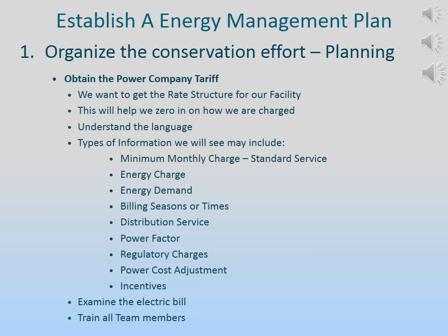This bill is a flat rate consumption, so anything we save is at the 5 cents per kilowatt hour. Also notice with this tariff, there are flat rate facility charges that we cannot do anything about. It is the consumption numbers we can change. The next page is the facility's rate structure. This is an important item to understand. Sometimes it becomes fairly technical and we may need some help understanding it.